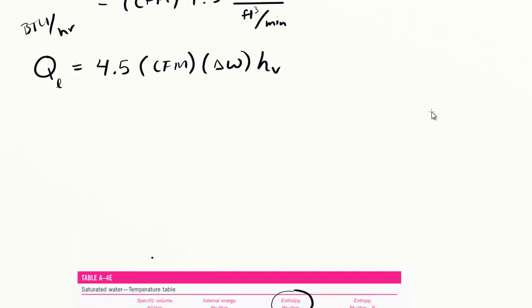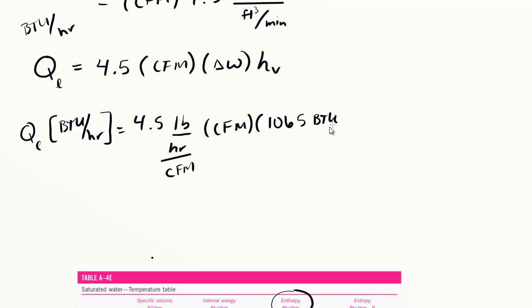Let's put this in. Q latent in BTU per hour equals 4.5 pounds per hour per CFM multiplied by the CFM of air multiplied by 1065 BTU per pound, multiplied by delta omega, or omega 2 minus omega 1, whatever that happens to be in our process.